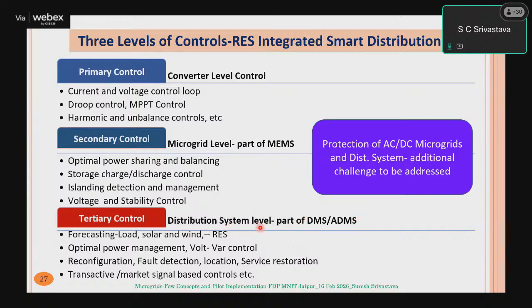So it is part of the distribution management system. But if you are managing large renewables, you are transitioning to an advanced distribution management system, which includes forecasting of not only load but renewables, optimal power management, volt-var control, and reconfiguration. In future, at the distribution level also, power will be purchased locally between two microgrids or between two consumers, prosumers. So transactive or market signal-based control will be there. Now to manage this, you require a local system operator. So the concept of the distribution system operator has been coined.